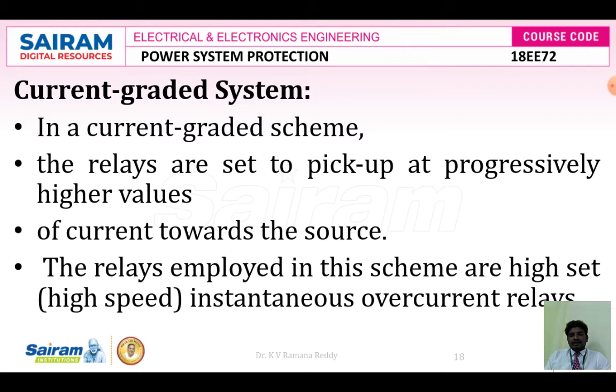Next system is called the current graded system. In a current graded system, the relays function based upon the preset value and pickup current, which is progressively set at higher values of current towards the source. The relays employed in this scheme are high speed instantaneous overcurrent relays.